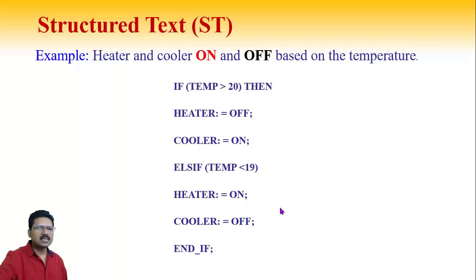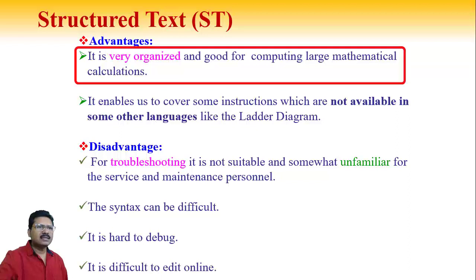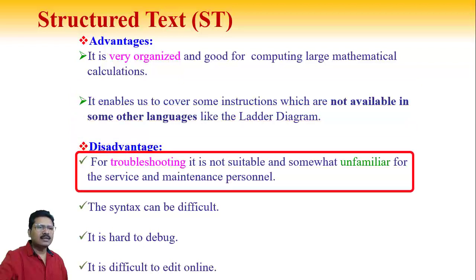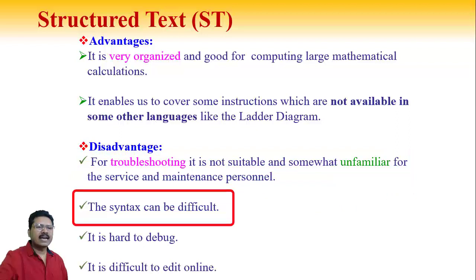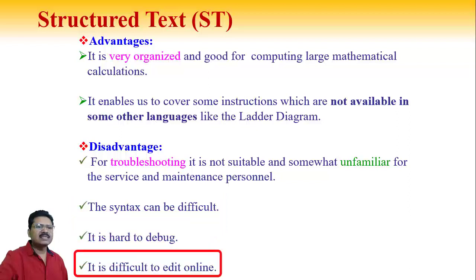The advantages of Structured Text: it is very organized and good for computing large mathematical calculations. It enables instructions that are not available in other languages like Ladder Diagram. As disadvantages: it is not suitable for troubleshooting and is somewhat unfamiliar for service and maintenance personnel. The syntax can be difficult, it is hard to debug, and it is difficult to edit online.